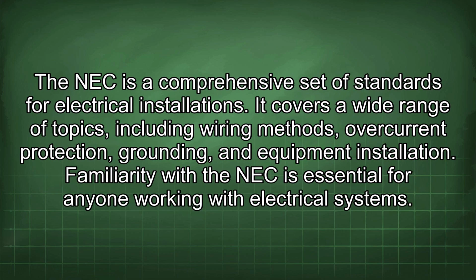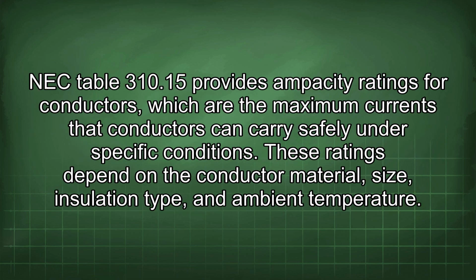The NEC is a comprehensive set of standards for electrical installations. It covers a wide range of topics, including wiring methods, overcurrent protection, grounding, and equipment installation. Familiarity with the NEC is essential for anyone working with electrical systems. NEC Table 310.15 provides ampacity ratings for conductors, which are the maximum currents that conductors can carry safely under specific conditions. These ratings depend on the conductor material, size, insulation type, and ambient temperature.